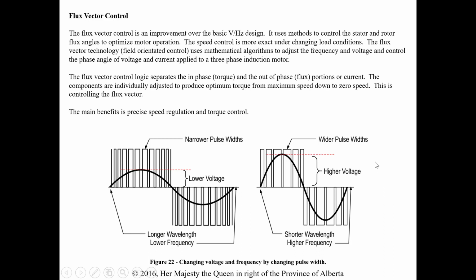Flux vector control, it's an improvement on the volts per hertz design. It uses methods to control the stator and rotor flux angles to optimize motor operation. The speed control is more exact under changing load conditions. So again, things can happen with your motor. You can load it up, take the load off, and this technology is way better at adjusting for that because it uses mathematical algorithms to adjust the frequency and voltage based on the phase angle. So flux vector control logic separates the in phase, so the torque. Again, think of our phasor diagram on the in phase component, and the out of phase, or the flux, the magnetic portion of current. Components are individually adjusted to produce optimum torque for maximum speed. This is controlling in the flux vector. So think about our vector diagrams when you're referring to this as well. Again, I would say probably a higher cost with this as well, but definitely a better way of doing it.